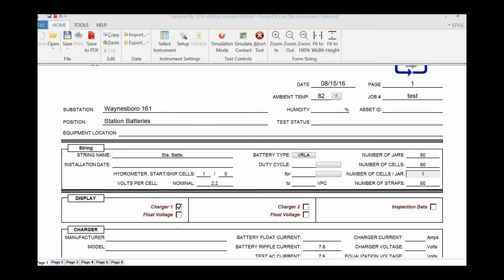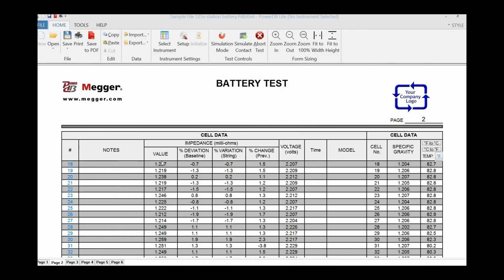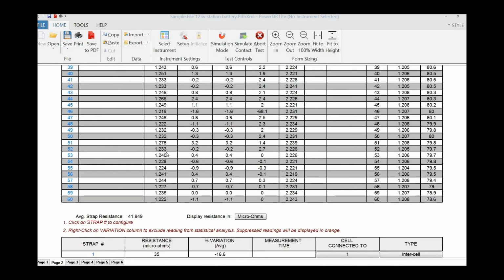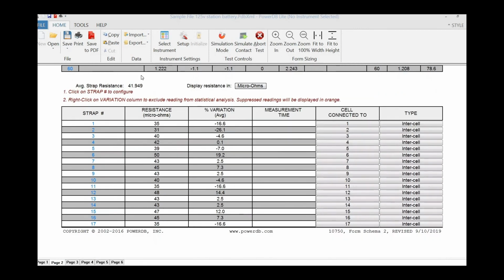To view intercell or strap data, go to page 2 and then scroll down. Following the cell data, you'll come to the strap data. Here you can view the average strap resistance, which is used for a reference during the strap analysis. You'll also see the resistance value for each strap measurement. This can be viewed in either microohms or milliohms.